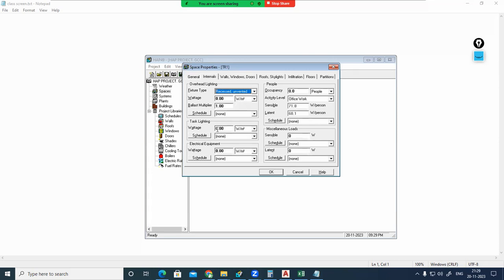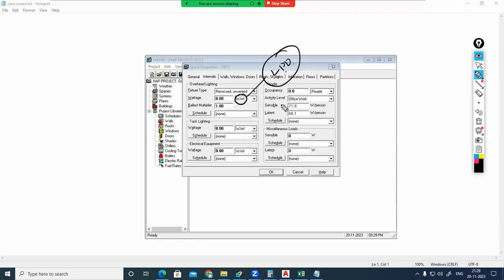Light fitting heat gain is by radiation only. That also we can give in two ways: either by watt per meter square value or by watts value. Watt per meter square means, if you are not having any light fitting drawings, if you are getting a plain drawing, you have to give the input. ASHRAE has studied a lot of buildings and arrived at a per meter square value for lighting. This watt per meter square data we call the LPD value, meaning lighting power density value.